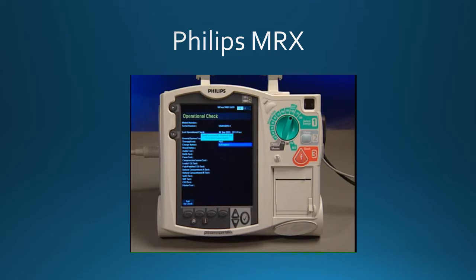To supplement these automatic tests, you should perform periodic shift checks and weekly shock tests or operational checks on the device. The American Heart Association recommends completing a shift check at the beginning of each change in personnel to help ensure that defibrillators are ready when needed. Philips provides a checklist to complete a shift check on the MRX, including the Ready for Use indicator and related accessories and supplies.